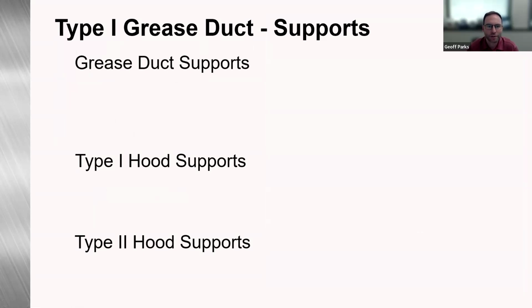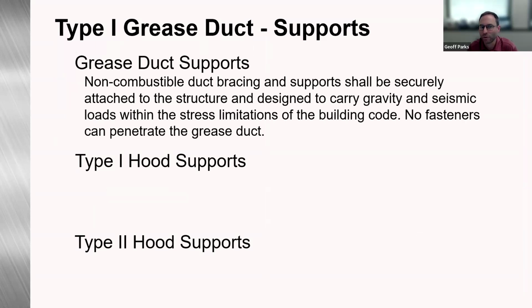Type 1 grease duct supports. So grease duct supports, non-combustible duct bracing and supports shall be securely attached to the structure and designed to carry gravity and seismic loads when required within the stress limitations of the building code. No fasteners can penetrate the grease duct. And also, anytime you have a duct cross section that's 24 inches or greater in any direction, you're going to have to design for the duct weight and 800 pounds at any point of that grease duct system. So that means you're going to have to heavy up your duct supports.